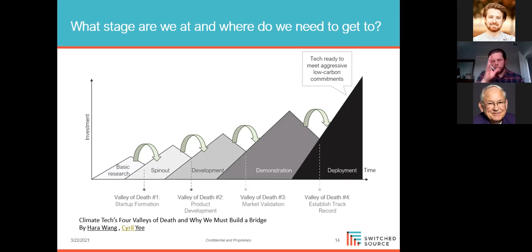This is what everybody would probably like me to talk through: the details of how our technology works. I won't dare do that with this audience. I'll just say the core trade-off we're making is this idea that if you take commodity off-the-shelf components and put them into a cascaded architecture, with building blocks rated for maybe 1200 or 1700 volts, stacked up to reach higher voltage levels in a partially rated converter design, you might come up with power flow control technologies at a lower price point than doing a transformation down to 480 volts, a back-to-back AC/DC/AC conversion, and stepping it back up with another transformer.